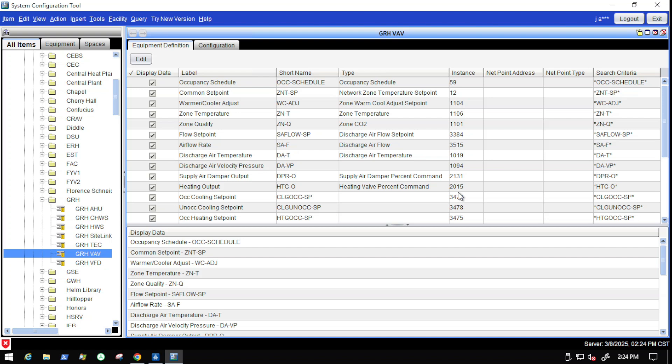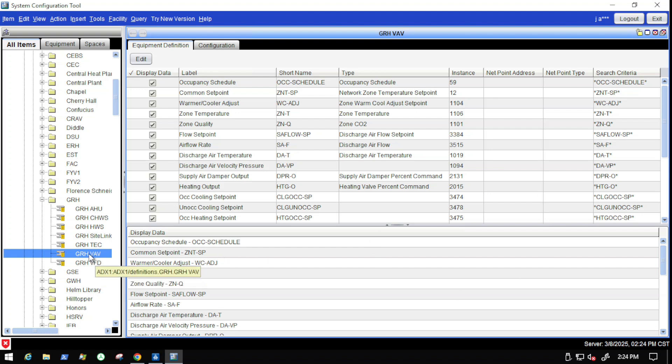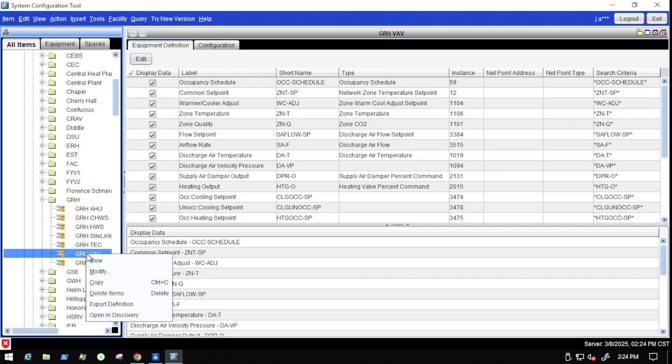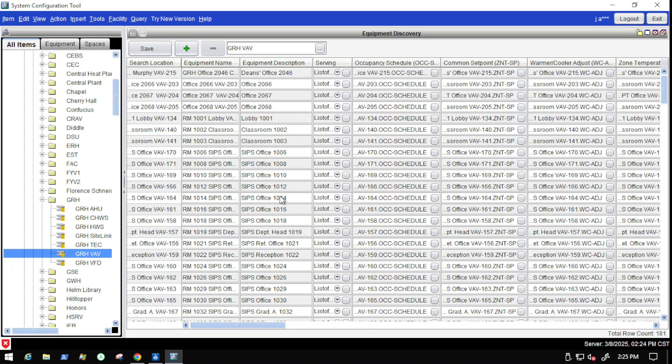And that instance ID may be different for different manufacturers, different types of VAVs and so on. And yes, you can use different manufacturers, different VAVs and everything else and pull them into the same equipment definition. Now, what I want to do is I want to go into the discovery mode. I'm going to right click on this particular equipment definition and I'm going to select open in discovery. And once I do that, it is going to pop up and show me all of the equipment that is associated with that particular equipment definition.